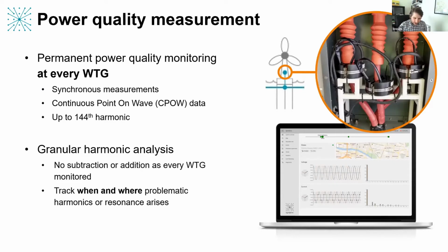And I kind of just want to add a bit more depth to some of the points that Sol and Tom have already touched on. With our sensing approach, every electrical sensor, every current and voltage sensor that we deploy, provides permanent and synchronous monitoring of the voltage or current at that location. What that means is we get waveform data streamed in continuously for the lifetime of that sensor. And from that waveform data, we can go well beyond what you can do with a simple RMS measurement. It means you can pick out all of the harmonics that are of interest.